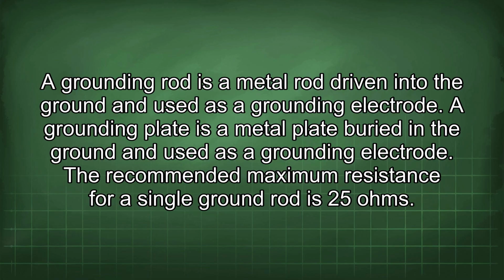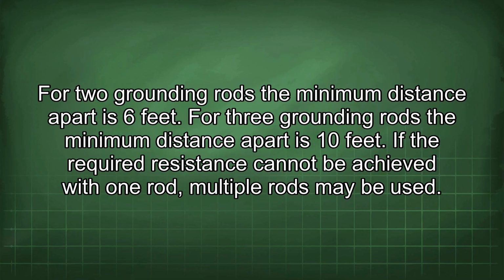The recommended maximum resistance for a single ground rod is 25 ohms. For two grounding rods, the minimum distance apart is 6 feet. For three grounding rods, the minimum distance apart is 10 feet. If the required resistance cannot be achieved with one rod, multiple rods may be used.